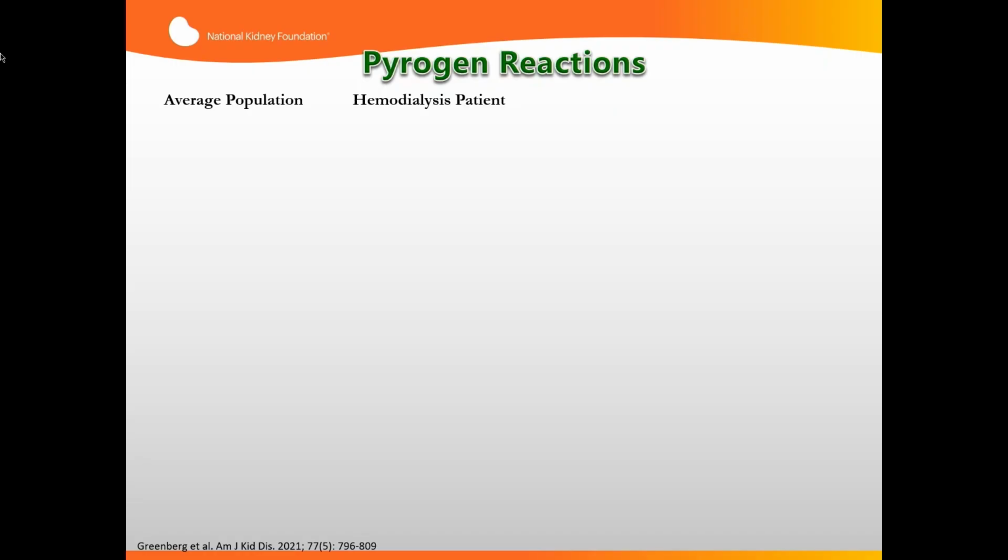Okay, so the last situation that can occur is pyrogen reaction. Let me put this in perspective for you. Your average non-dialysis patient drinks approximately 14 liters per week, about roughly 2 liters per day. Well, guess what? Your hemodialysis patient is exposed to approximately 360 liters per week.